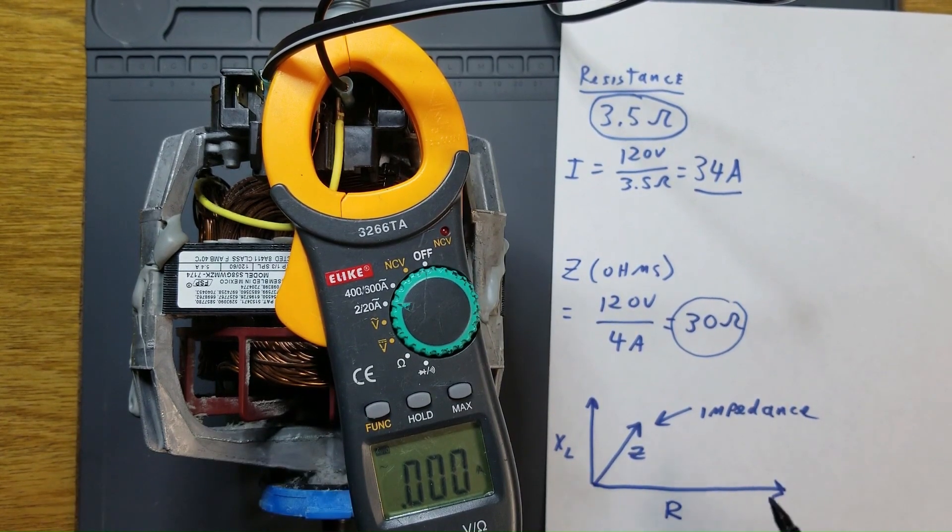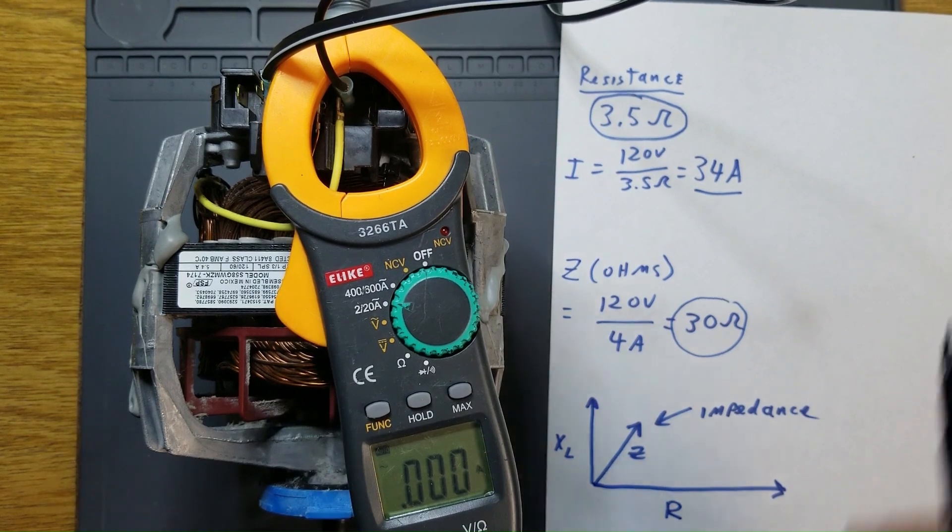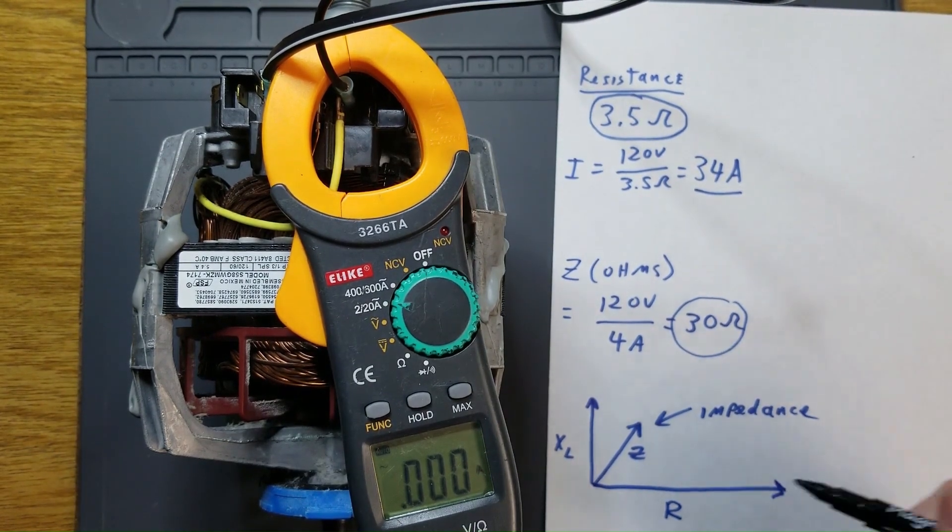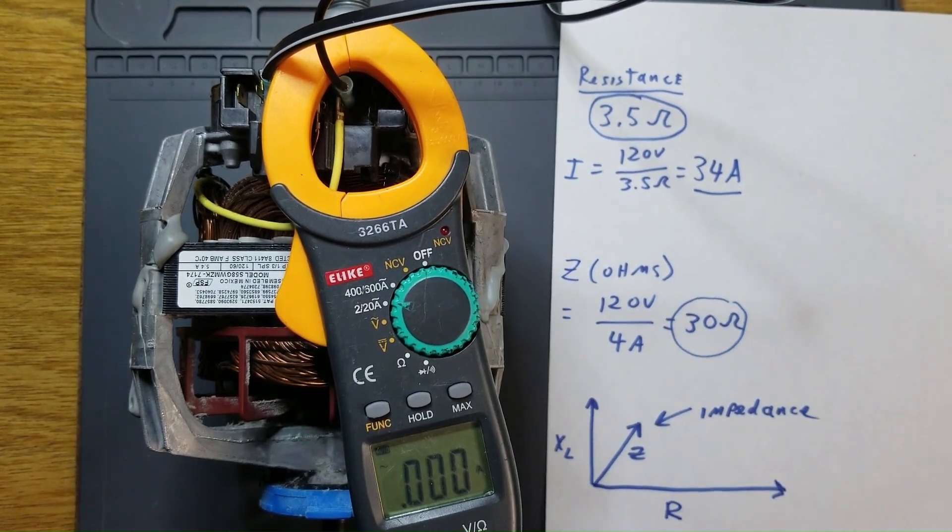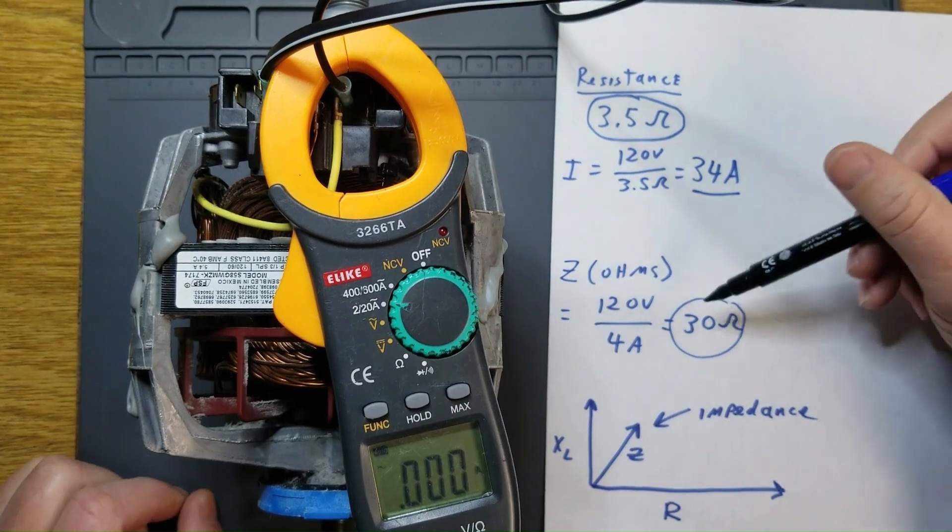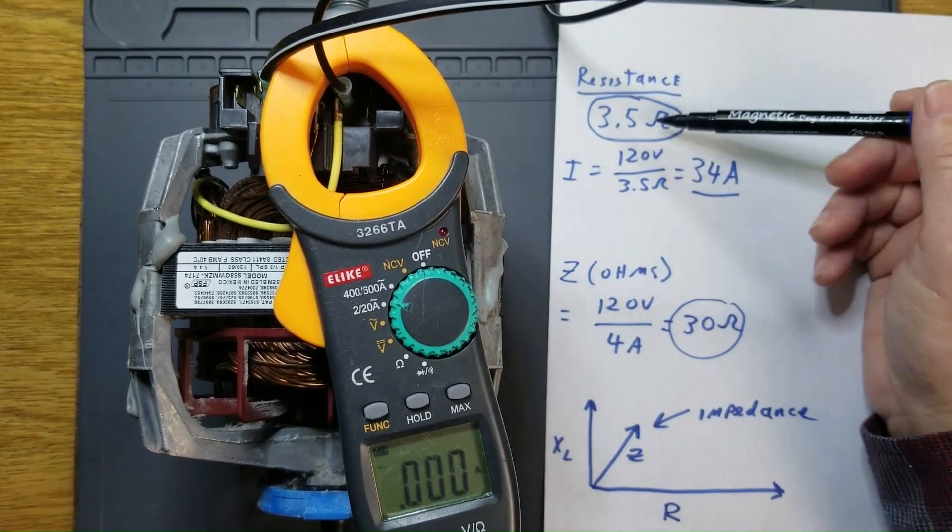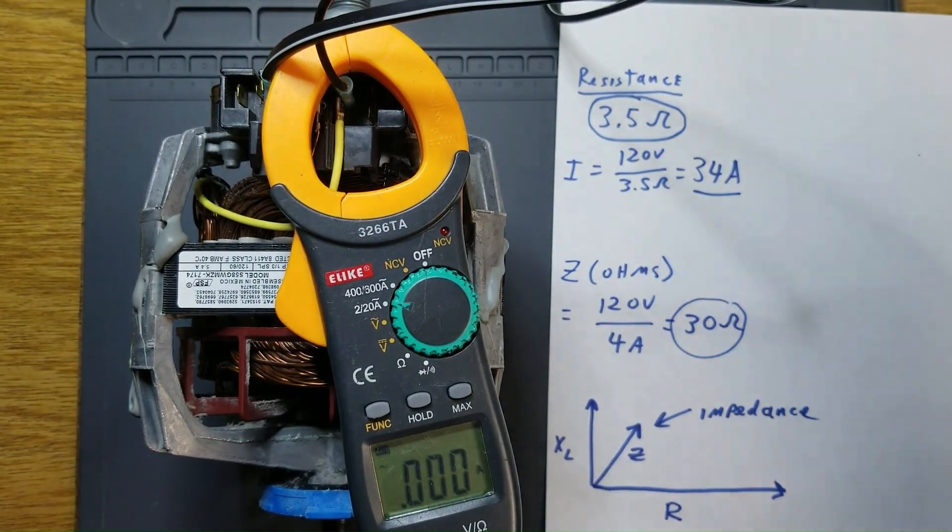The inductive reactance of this motor is much higher than our measured resistance, and the resulting impedance is around 30 ohms, which leads to the much lower current draw than we calculated if we were to rely on our static reading.